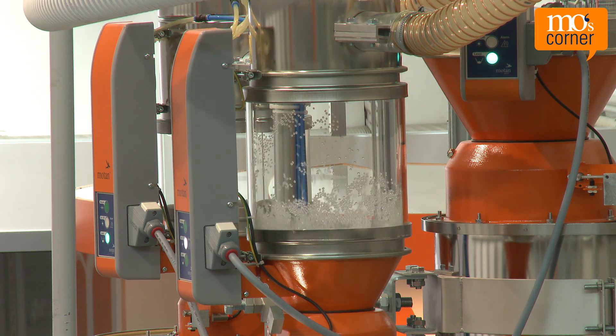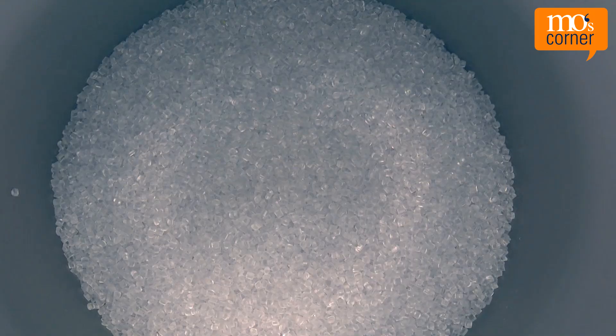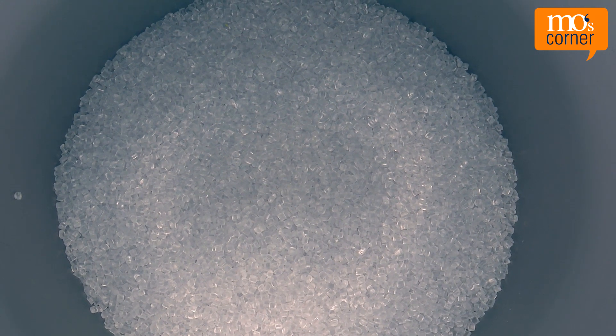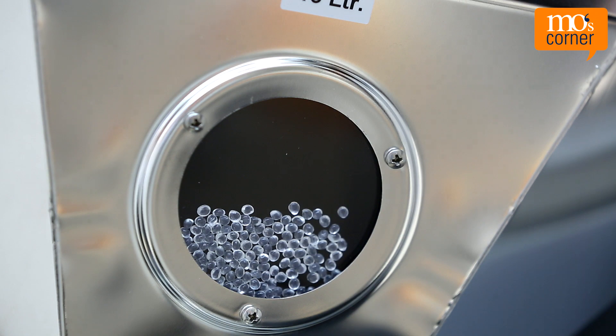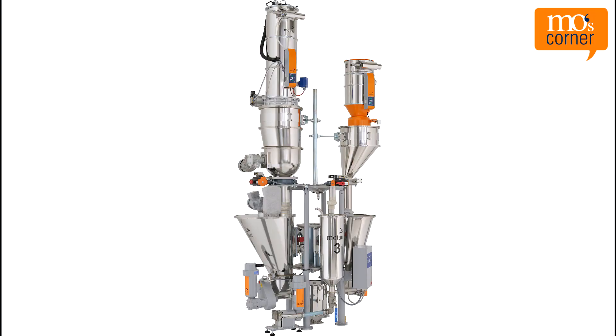The material loader has filled a refilling hopper above the dosing station — this has enough volume to refill the dosing hopper in a very short amount of time. As soon as the control gives the signal to start refilling, the dosing hopper is filled in one go. This needs to happen as quickly as possible so that the volumetric dosing phase is as short as possible.